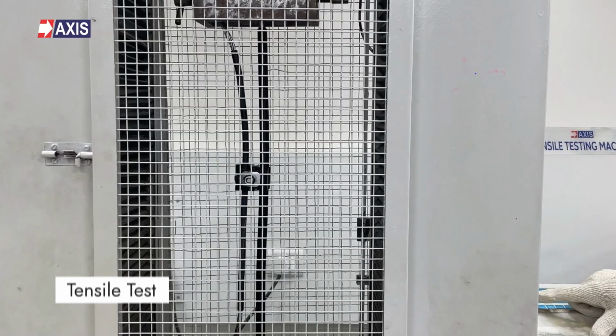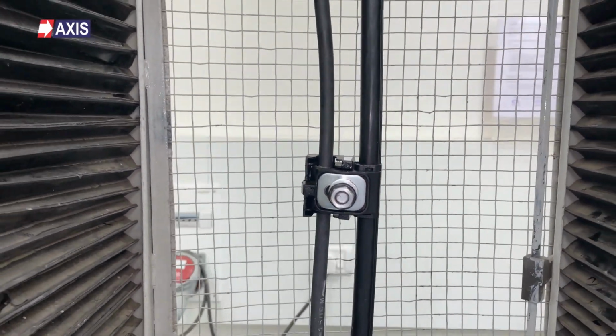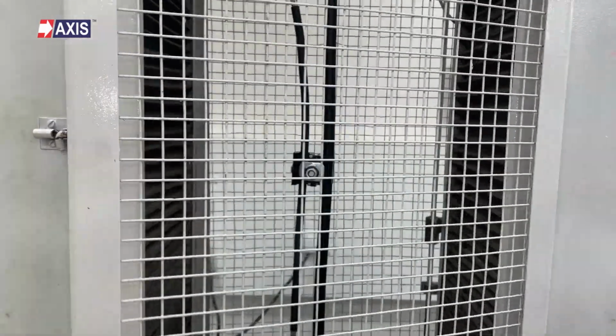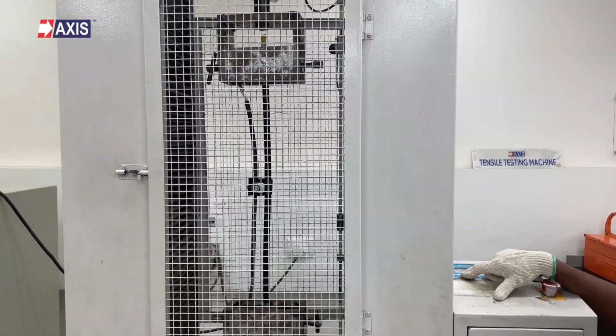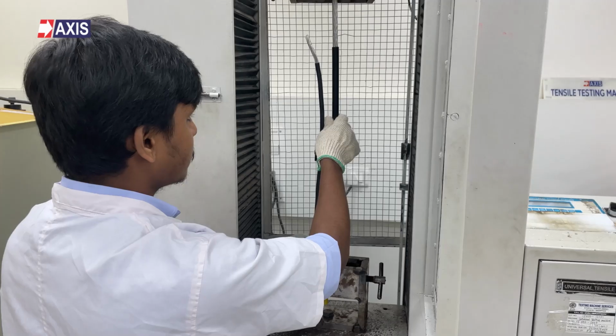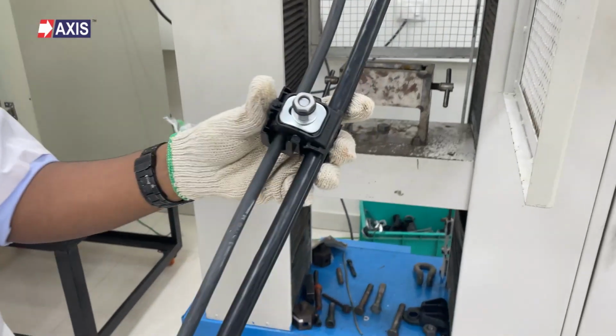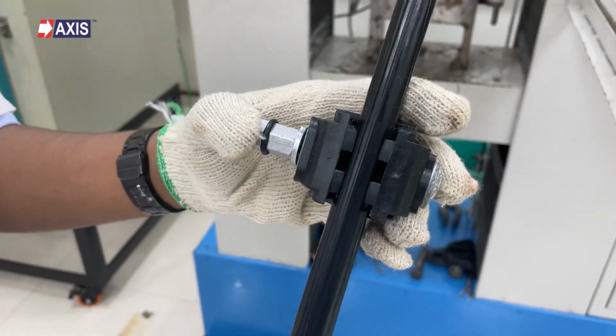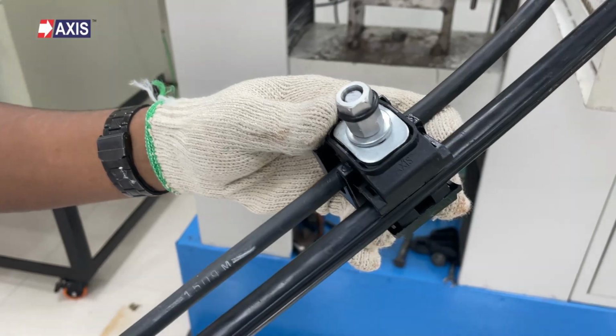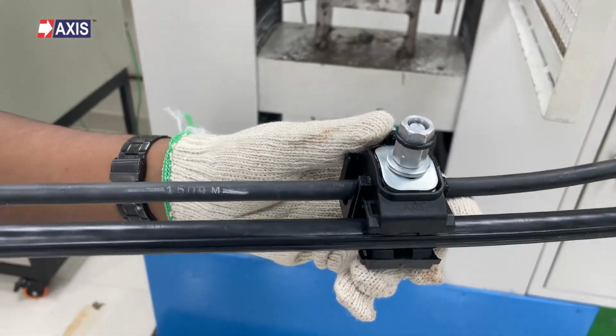Now, test number 4, the tensile test. The aim of this test is to determine if the connector can withstand the required tensile load without damaging the cable it is connected to. But how do you perform this test? You set the tensile load value and duration according to the NFC 33020-2013 standard and then apply the load for 1 minute. After the test, you check for 2 things. Firstly, the IPC should not be damaged. And secondly, the conductor should not slip from the connector. If either occurs, the sample fails and does not comply with the standard. As you can see, our IPC remained undamaged and there was no slippage of the conductor. This confirms that the Axis IPC can handle the required tensile load.